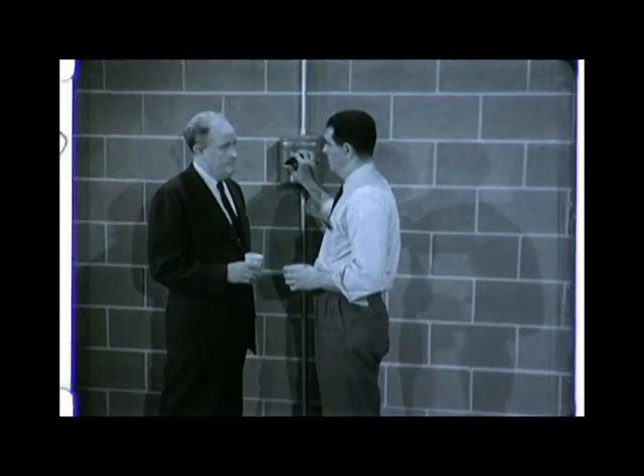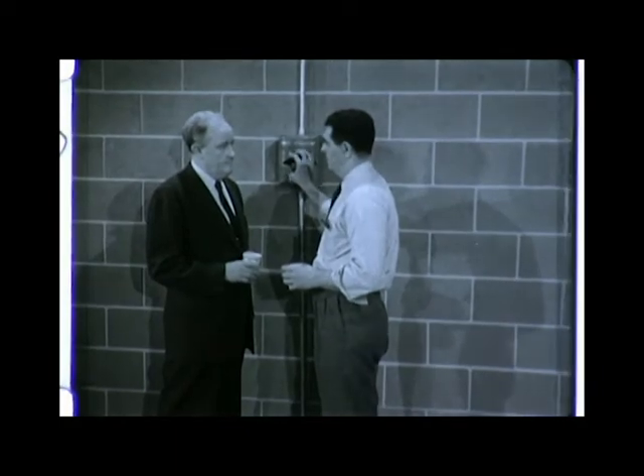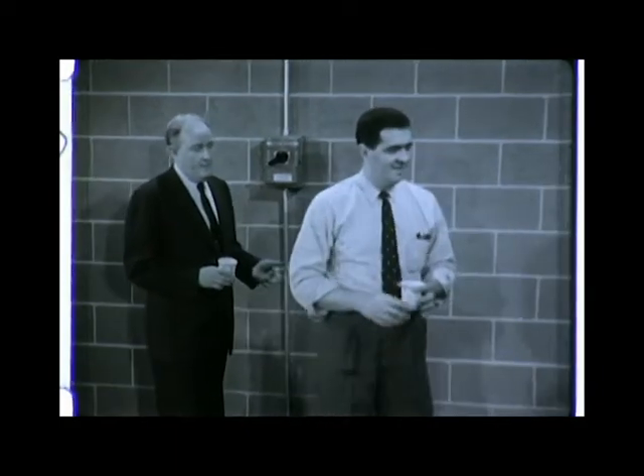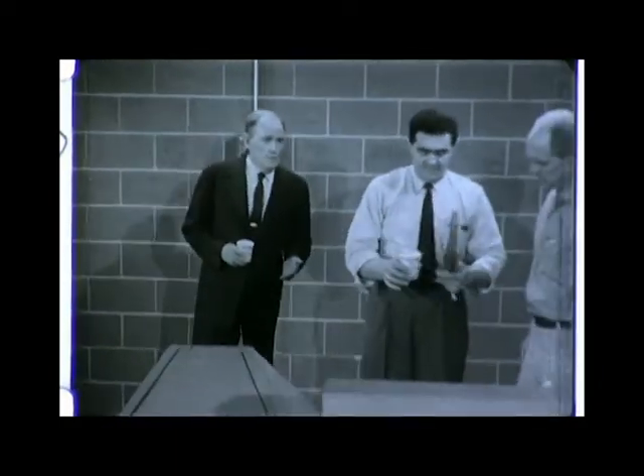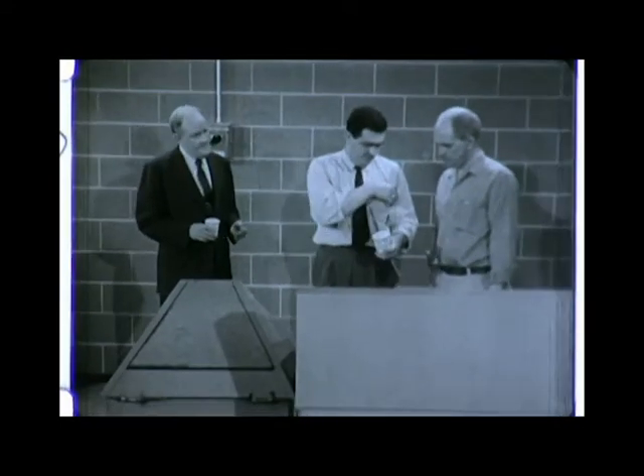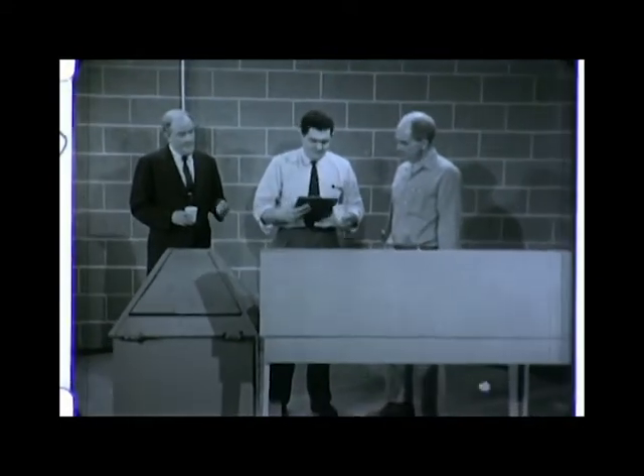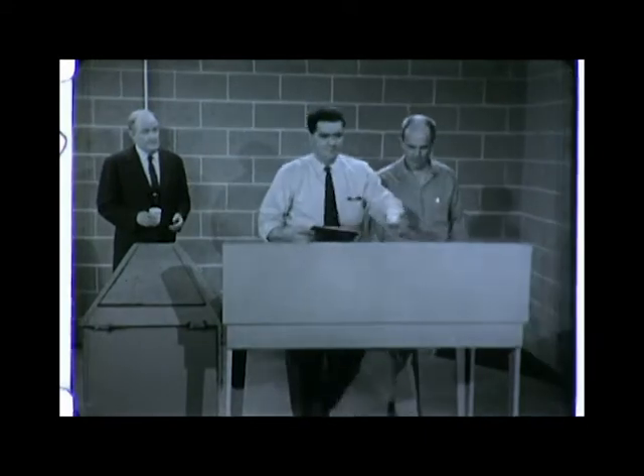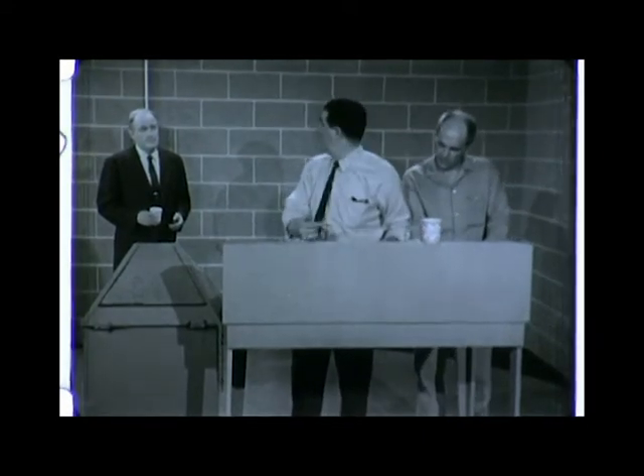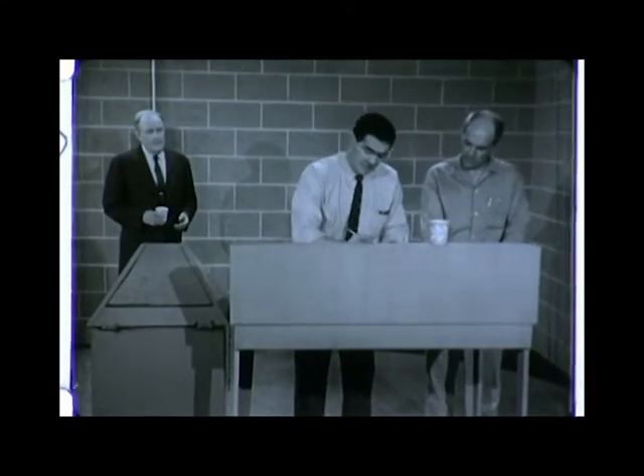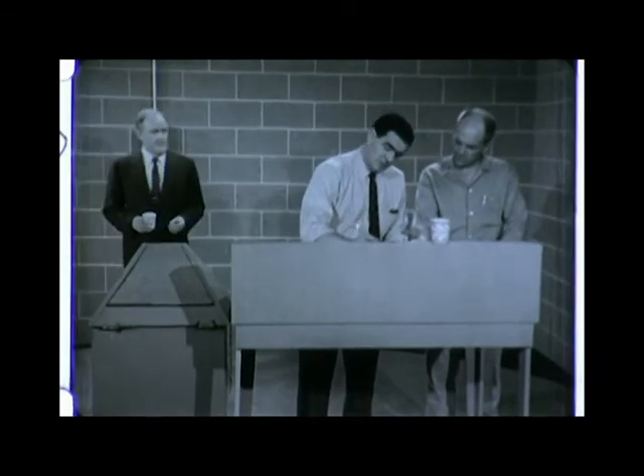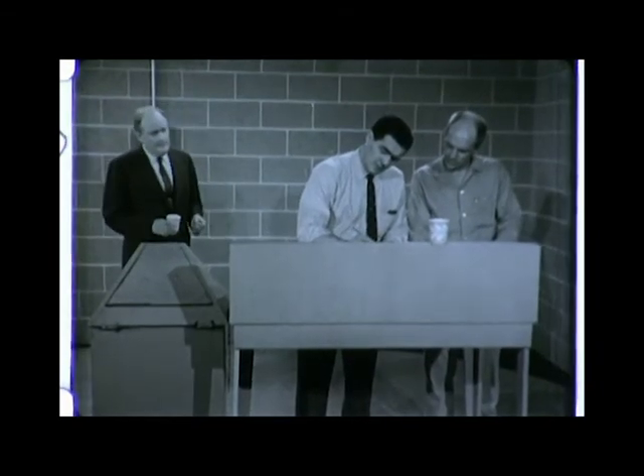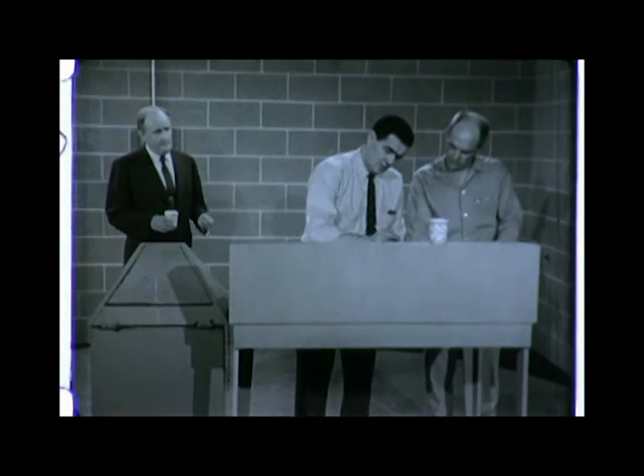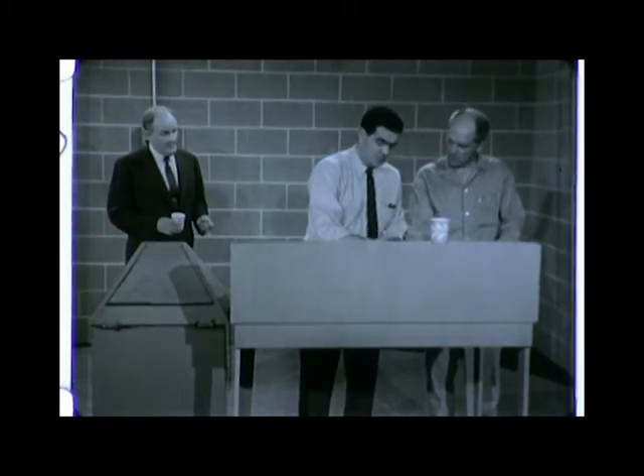Now let's see how Mike Perkins handles the indifferent customer. In a sense, Tony, they both do the same thing. Both fuses melt when the current becomes excessive. The difference is in how they melt and how much protection they give you. Go ahead, Mike, I'm listening. As I was saying, the difference is in how much protection they give you. Now the CLF will interrupt even a severe short circuit without explosion or fire, while a conventional fuse...